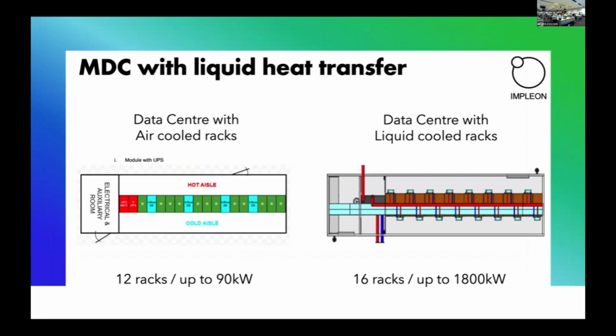Another comparison is about open source modular data centers. On the left, you see an air-cooled open source modular data center. On the right, a liquid-cooled open source modular data center for AI. You see that in the same container with air, you can achieve 12 racks with 90 kilowatt. With liquid cooling for AI, you can achieve 16 racks up to 1.8 megawatt. So the gap is 20 times. The same can be applied at bigger scale. It's just an example of how you decarbonize. So let's say you will have 20 times more performance capacity, but the footprint of the building will remain the same.